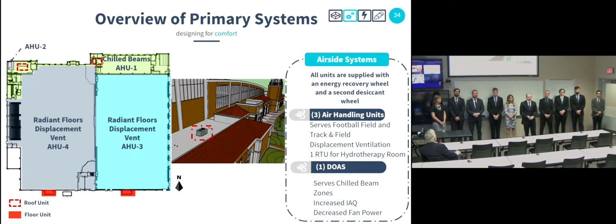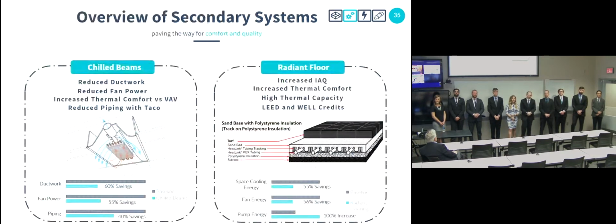These 2 units and AHU-1 utilize a second desiccant wheel in addition to the primary energy recovery wheel. This second desiccant wheel wraps around the cooling coil to provide increased dehumidification and reduces the reheat energy requirements. AHUs 3 and 4 are also paired with radiant floor systems to provide for the remaining sensible heating and cooling loads of the fields. And now to talk a bit more about our secondary systems and why we chose them.